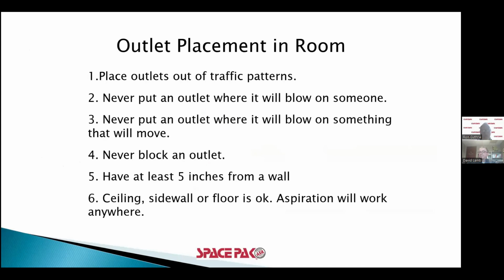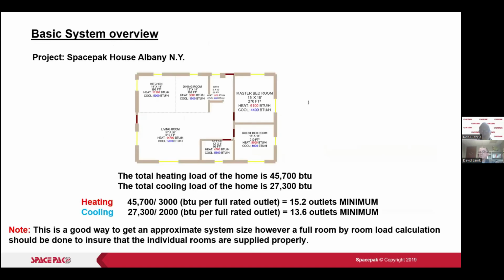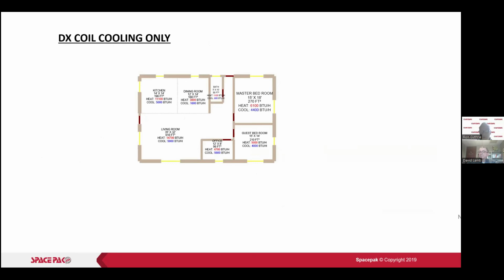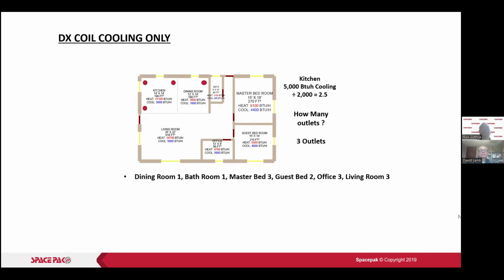All right, room by room load. We went through that, and this example covers it. I'm going to go through this quickly, because the largest point of this is that we do this exercise for both heating and cooling: how many BTUs we put into a room versus our heating and cooling loads. So we look at both our heating load and cooling load.